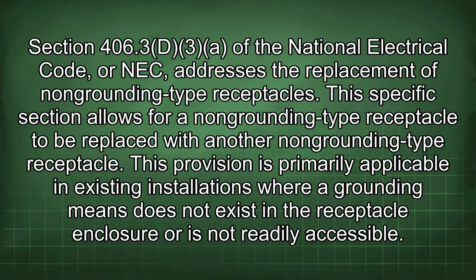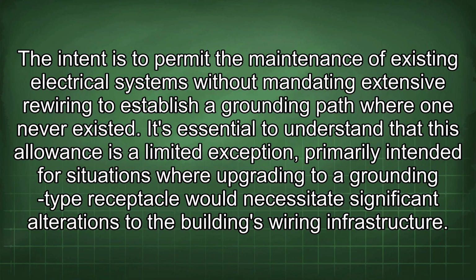Section 406.3d3 of the National Electrical Code, or NEC, addresses the replacement of non-grounding type receptacles. This specific section allows for a non-grounding type receptacle to be replaced with another non-grounding type receptacle. This provision is primarily applicable in existing installations where a grounding means does not exist in the receptacle enclosure or is not readily accessible. The intent is to permit the maintenance of existing electrical systems without mandating extensive rewiring to establish a grounding path where one never existed. It's essential to understand that this allowance is a limited exception, primarily intended for situations where upgrading to a grounding type receptacle would necessitate significant alterations to the building's wiring infrastructure.